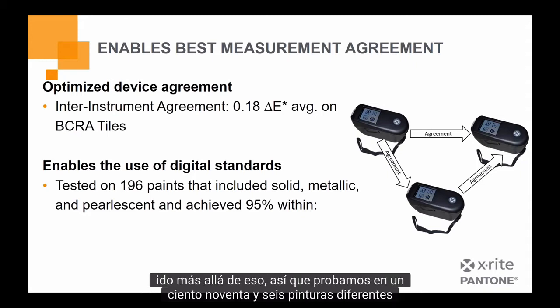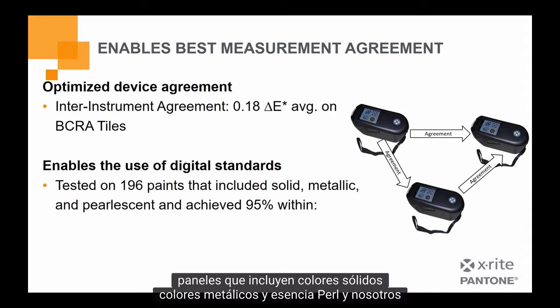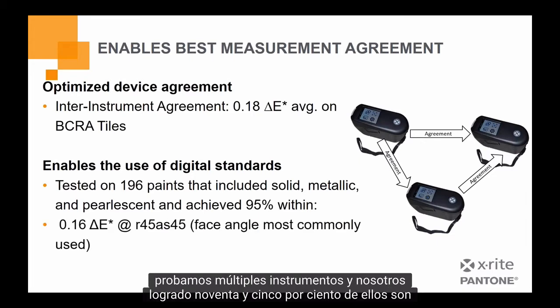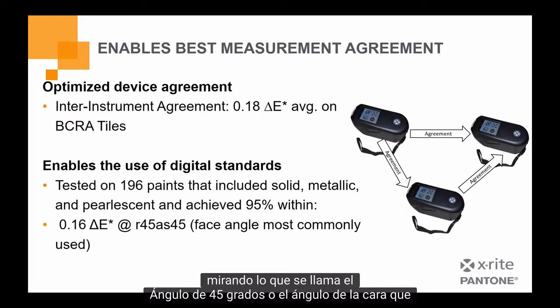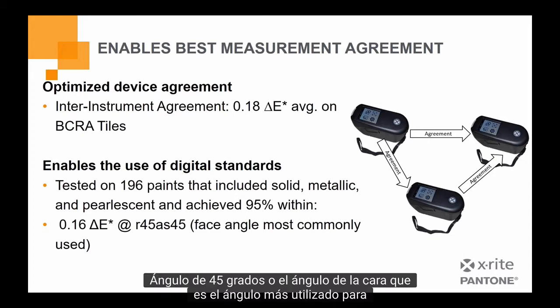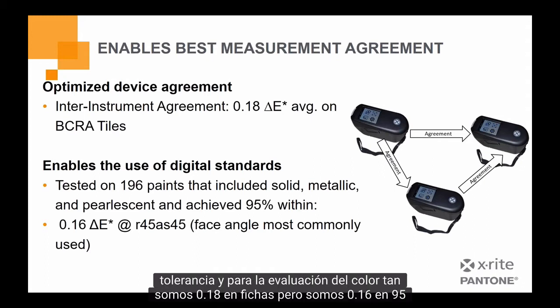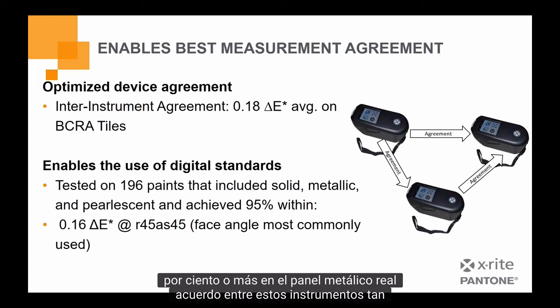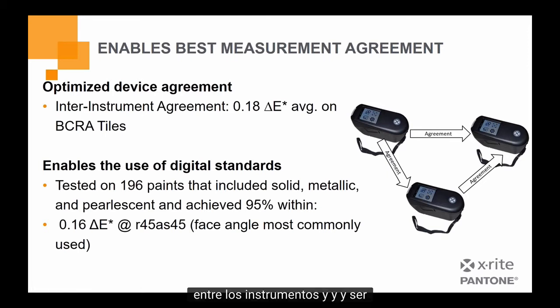And we've actually gone beyond that. So we tested on 196 different paint panels that included solid colors, metallic colors, and pearlescence. We tested multiple instruments, and we achieved 95% of them within 0.16 delta E of each other, looking at what's called the 45-degree angle, or the face angle, which is the most commonly used angle for tolerancing and for color evaluation. So we're 0.18 on tiles, but we're 0.16 on 95% or more on actual metallic panels. So we've got confidence that you can use these instruments to share data between the instruments and be able to have confidence in the results.